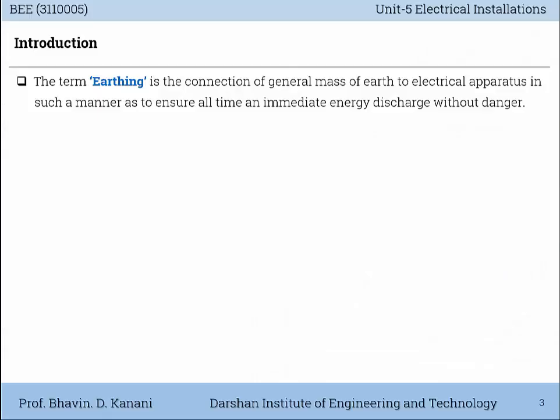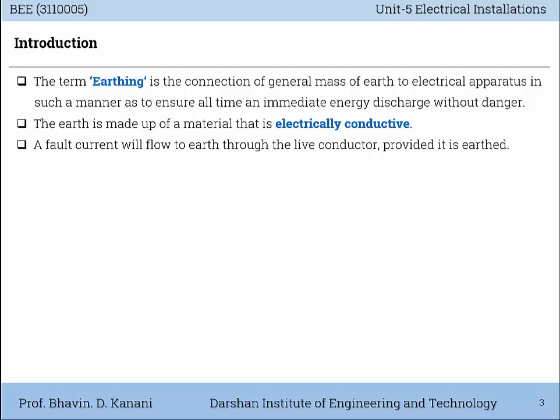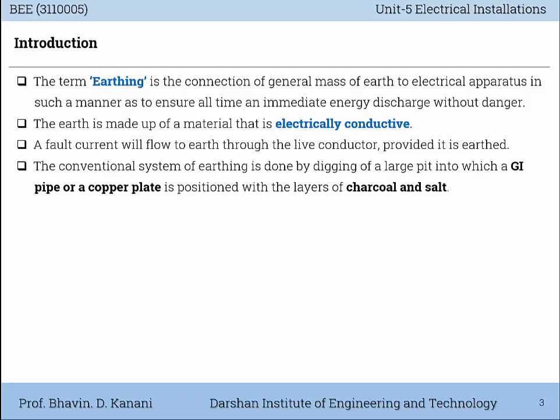Introduction. The term earthing is the connection of the general mass of Earth to electrical apparatus in such a manner as to ensure at all times an immediate energy discharge without danger. The earth is made up of a material that is electrically conductive. A fault current will flow to the earth through the live conductor, provided it is earthed. The conventional system of earthing is done by digging a large pit into which a GI pipe or a copper plate is positioned with layers of charcoal and salt.